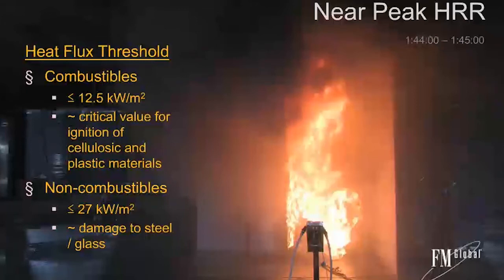The other number that we'll look at is for non-combustibles, and here, again, FM Global's datasheet 1-20 uses the value of 27 kilowatts per meter squared, and that represents the nominal value where you start to see damage to glass or steel. So this could be a sensitive piece of process or expensive piece of process equipment, and it could just as easily be a building column, a structural element of the building that you want to make sure isn't damaged.